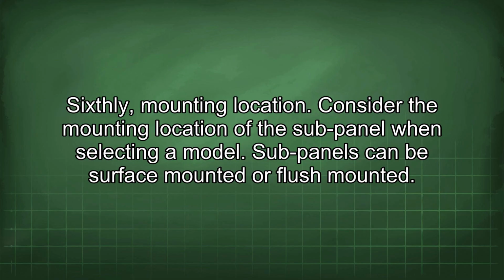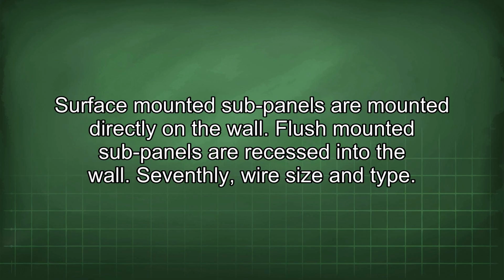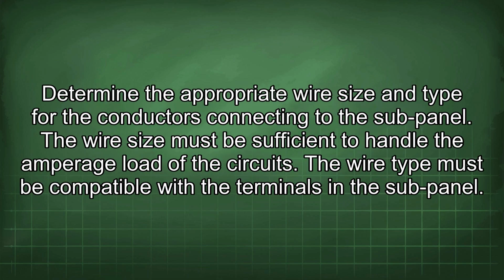Sixthly, mounting location. Consider the mounting location of the sub-panel when selecting a model. Sub-panels can be surface-mounted or flush-mounted. Surface-mounted sub-panels are mounted directly on the wall. Flush-mounted sub-panels are recessed into the wall. Seventhly, wire size and type. Determine the appropriate wire size and type for the conductors connecting to the sub-panel. The wire size must be sufficient to handle the amperage load of the circuits. The wire type must be compatible with the terminals in the sub-panel.